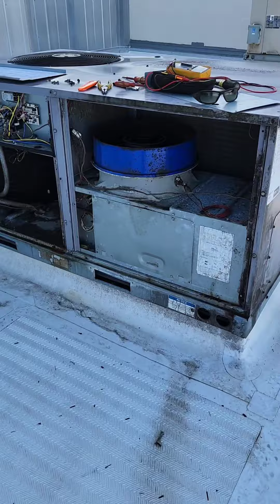So pretty much going through this unit, troubleshooting it - there's a smoke sensor right there in the supply. Panels are off to the side; never want to put them on condenser coils or anything like that, you'll eventually puncture them. That's always a no-no, leaning panels against any coils.